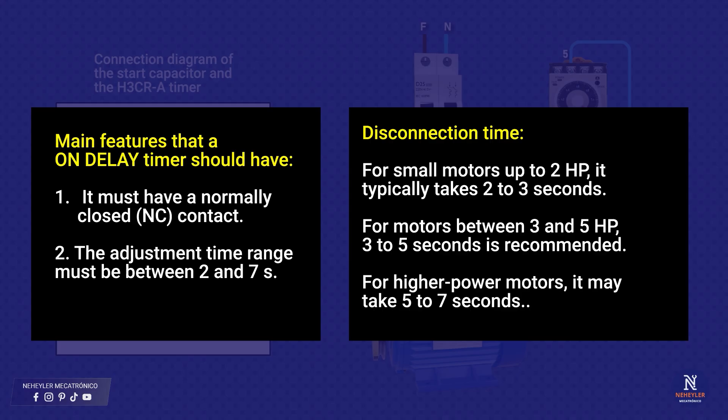That time can vary depending on the motor power. For small motors up to 2 horsepower, normally 2 to 3 seconds is enough. In motors of 3 to 5 horsepower, between 3 and 5 seconds is recommended. And in motors of greater power, it may take 5 to 7 seconds, always adjusting according to the motor response.